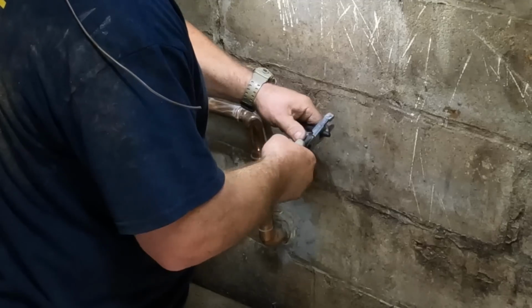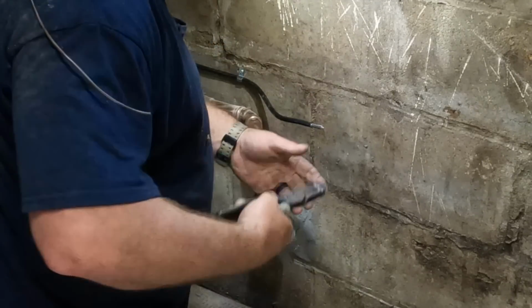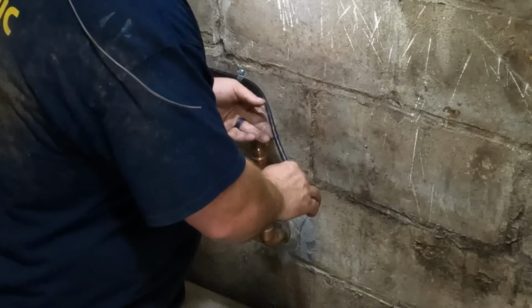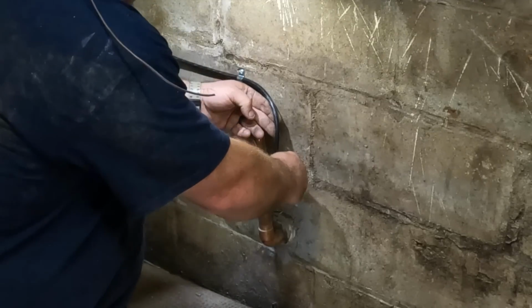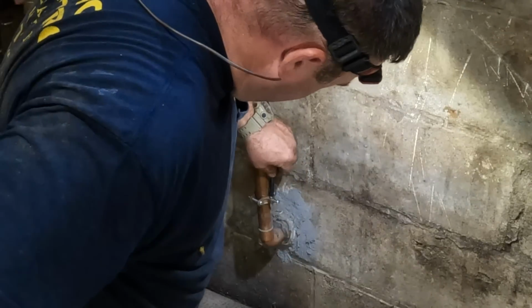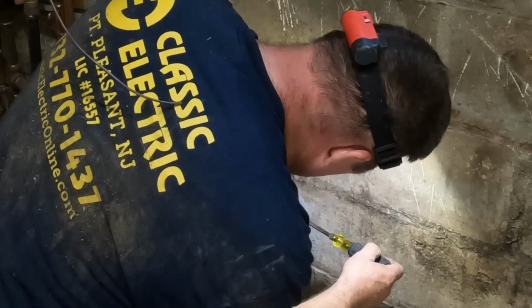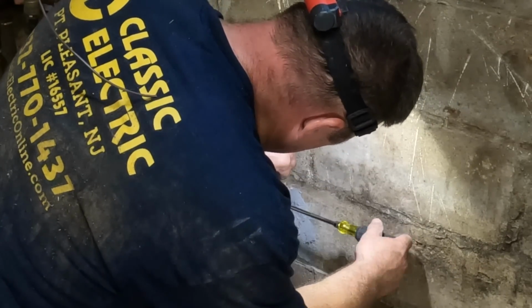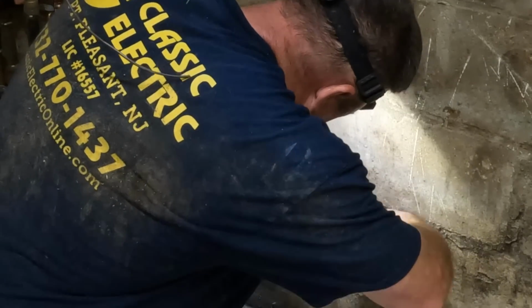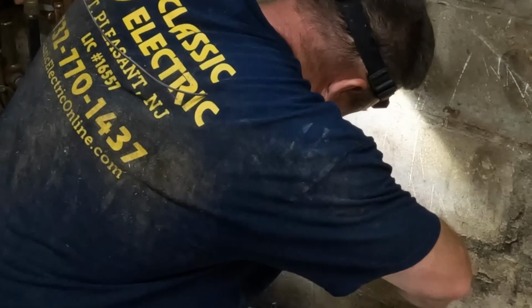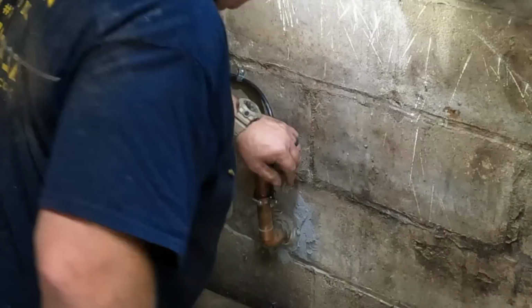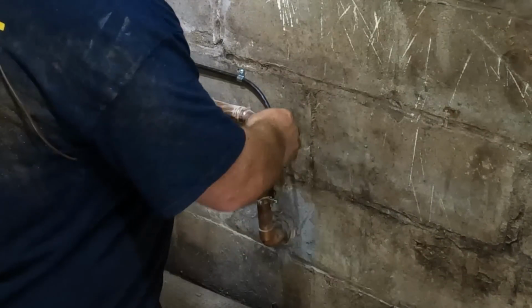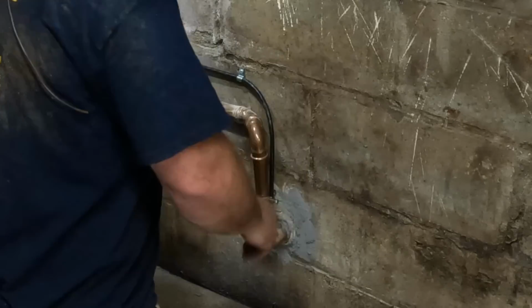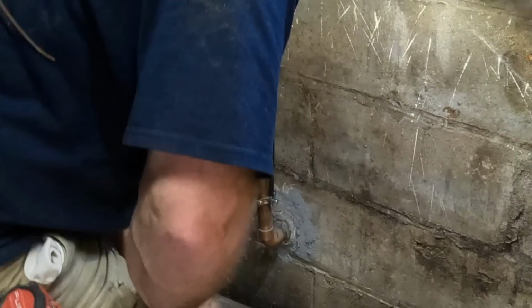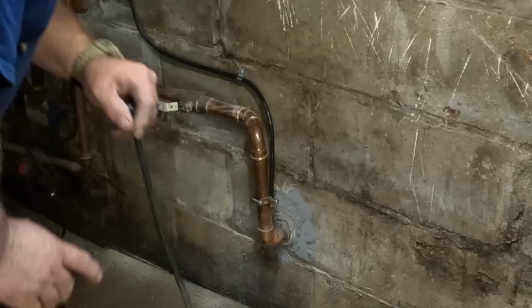So I put the clamp on there. I'm not sure. Usually I have different clamps, but I decided to use this brass one for no particular reason, only because I had it on the truck. And so what this does here is this bonds the grounding electrode conductor to the actual electrode so that you can limit the potential for current to flow on this copper water pipe and, of course, the water system throughout the house.